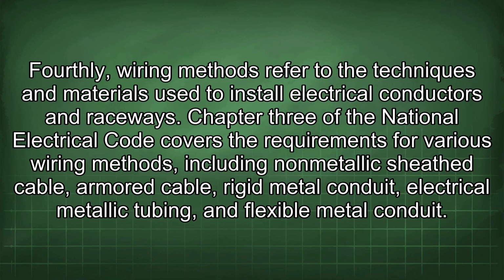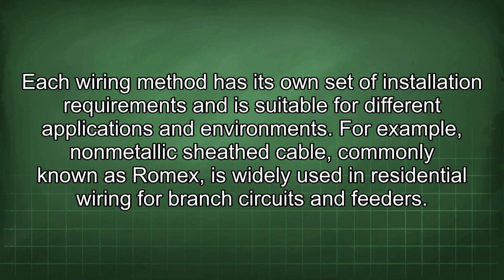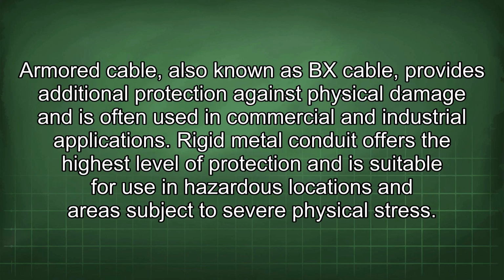Fourthly, wiring methods refer to the techniques and materials used to install electrical conductors and raceways. Chapter 3 of the National Electrical Code covers the requirements for various wiring methods, including non-metallic sheathed cable, armored cable, rigid metal conduit, electrical metallic tubing, and flexible metal conduit. Each wiring method has its own set of installation requirements and is suitable for different applications and environments. For example, non-metallic sheathed cable, commonly known as Romex, is widely used in residential wiring for branch circuits and feeders. Armored cable, also known as BX cable, provides additional protection against physical damage and is often used in commercial and industrial applications. Rigid metal conduit offers the highest level of protection and is suitable for use in hazardous locations and areas subject to severe physical stress.